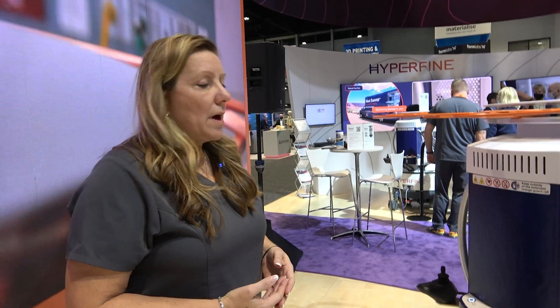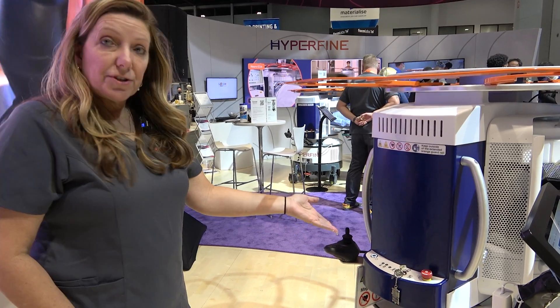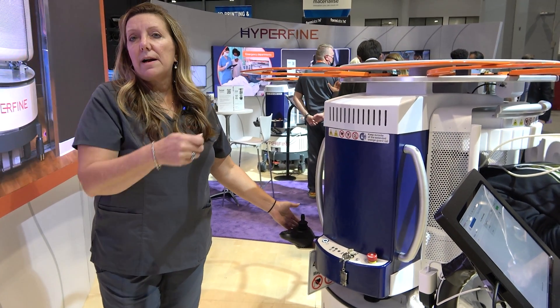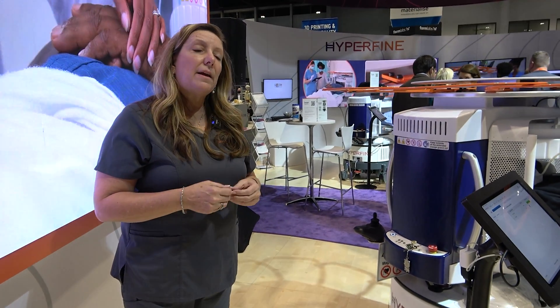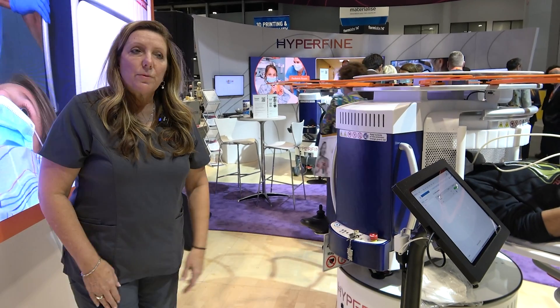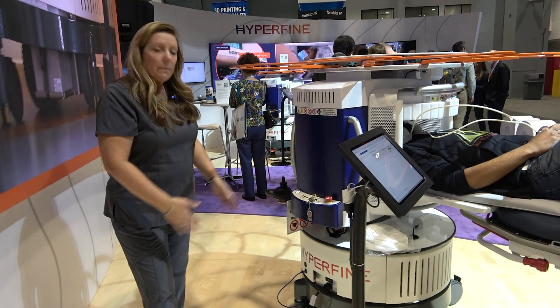This is really a point-of-care portable MRI. We can drive it right into the ICUs and emergency departments. We have a drive mode where we use a joystick to maneuver around hospital rooms to get to the top of the patient's bed. We can go in any standard size elevator — we don't need any special service elevator. We plug into a regular 110 outlet, nothing extra needed. All the electronics are housed down below — it's a pretty modular unit.